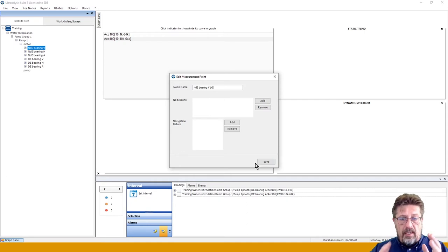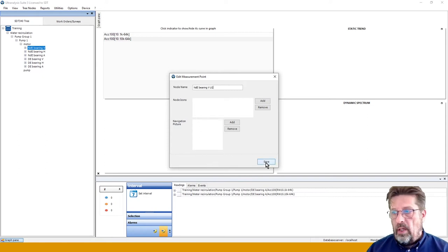So I can say, show me all the motors which do not have sealed bearings. They are lubricated with grease, and I can extract them out and take a look. There can be a million reasons for that, but one of the reasons can be, yes, we are doing great condition monitoring, but it seems that we have a lot of problems on grease lubricated bearings, so let's talk to the lube team. That's one of the options. So having it easily filtered is quite interesting and quite a good thing.